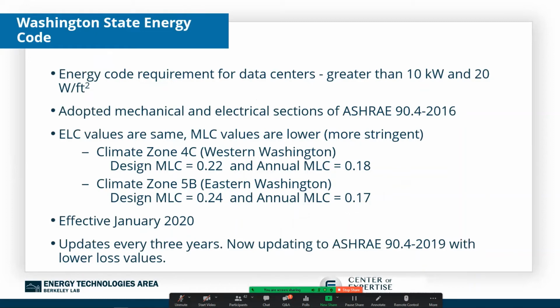The Washington State Energy Code essentially borrows heavily from the very first version of ASHRAE 90.4. It has those same electric loss component values, and slightly more stringent mechanical load component values. Partly that's a reflection of the different climate, but it's also Washington's desire to be a bit tighter. Those were initially effective in January 2020. It's on a 3-year update cycle, just like ASHRAE 90.4, and they're in the process of updating to the current standard, ASHRAE 90.4 for 2019.